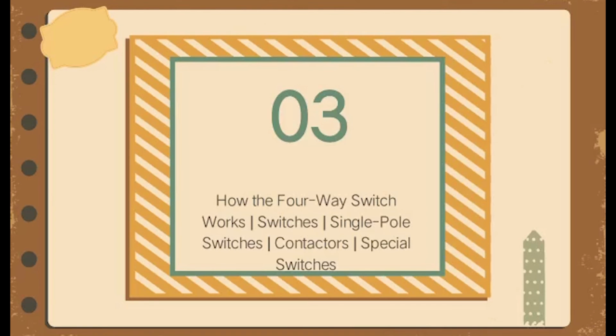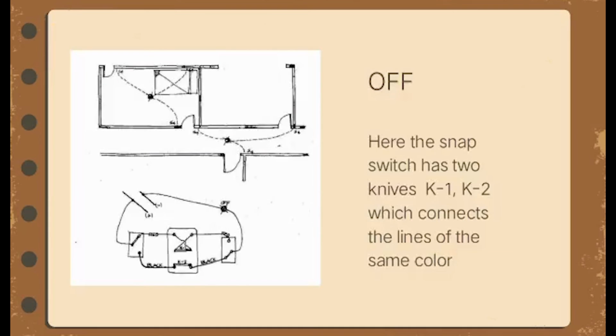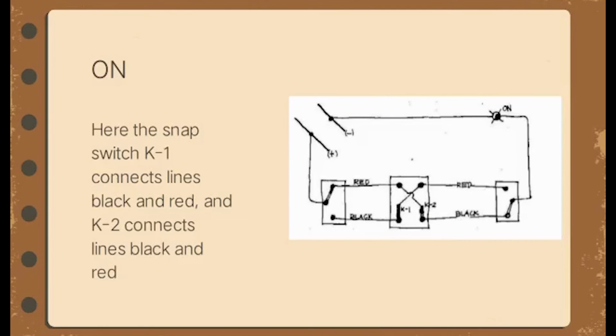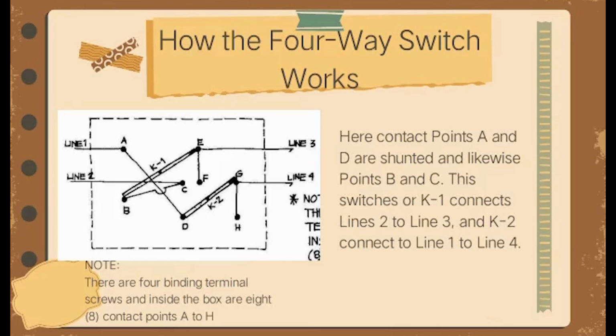How the four-way switch works: switches, single pole switches, contactors, special switches. Off. Here, the snap switch has two knives, K-1 and K-2, which connects the lines of the same color. On. Here, the snap switch K-1 connects lines black and red, and K-2 connects lines black and red. How the four-way switch works: here contact points A and D are shunted, and likewise points B and C. These switches, or K-1 connects line 2 to line 3, and K-2 connects line 1 to line 4.